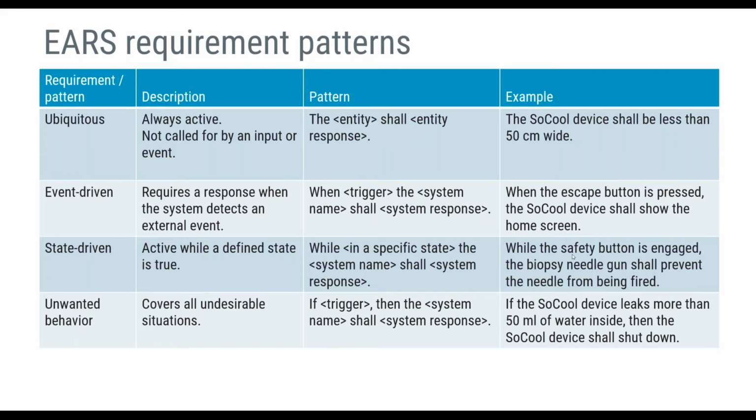Or while the safety button is engaged, the biopsy needle gun shall prevent the needle from being fired. And we also have an example of an unwanted behavior. If the SoCool device leaks more than 50 milliliters of water inside, then the SoCool device shall shut down. And this is almost like writing code.